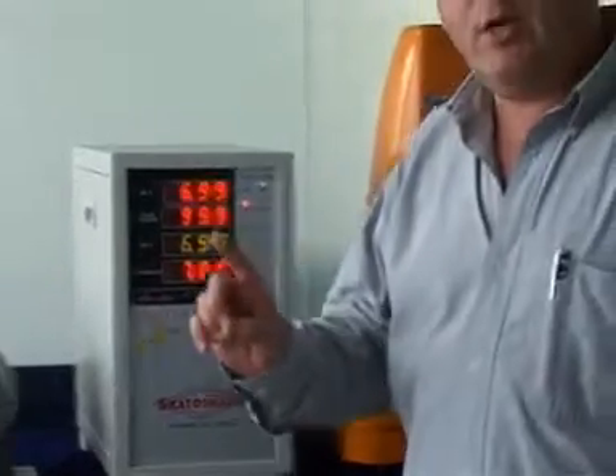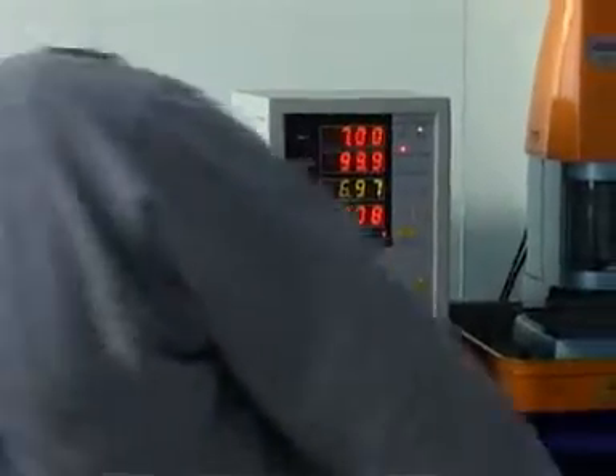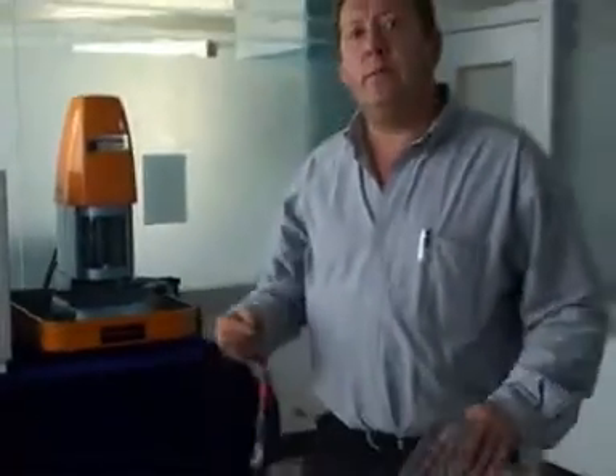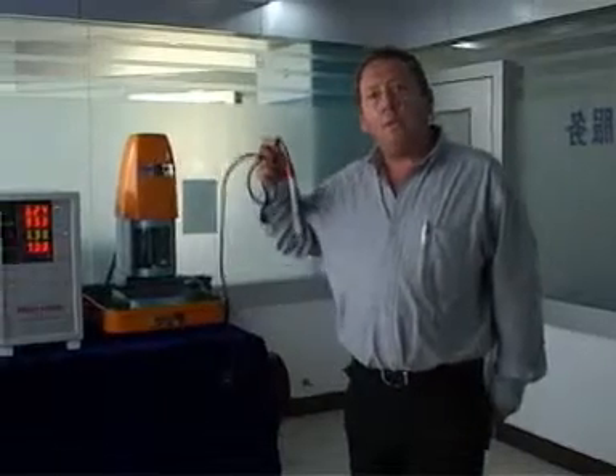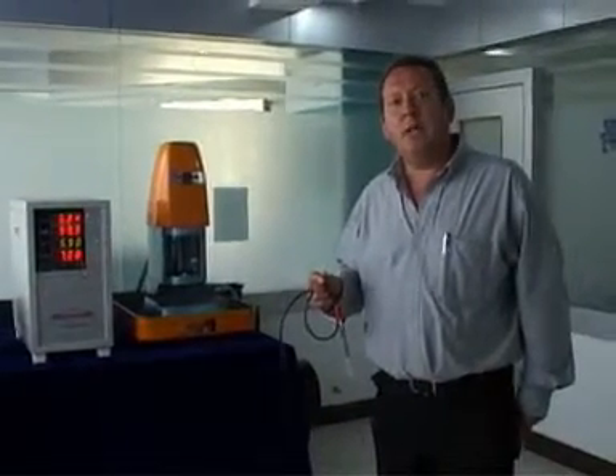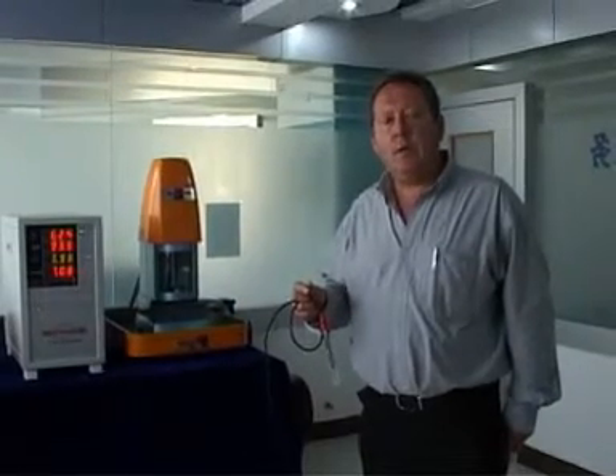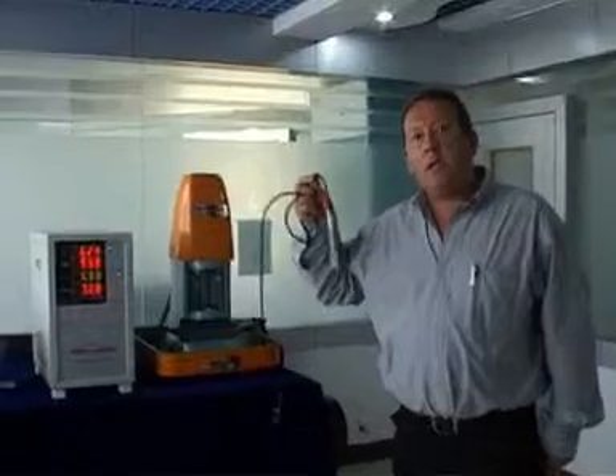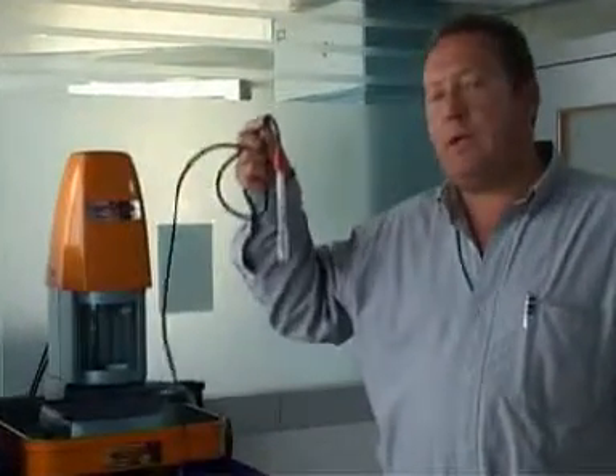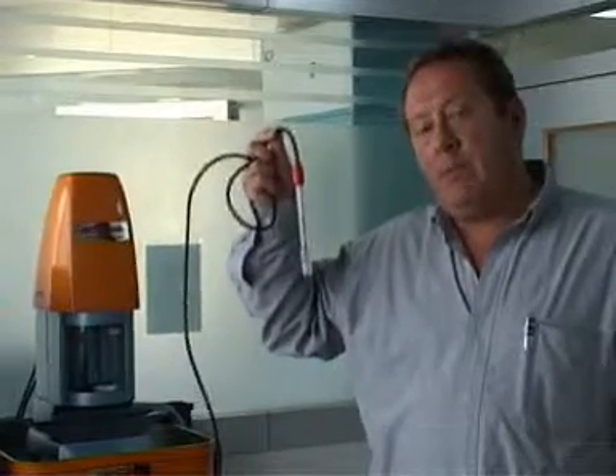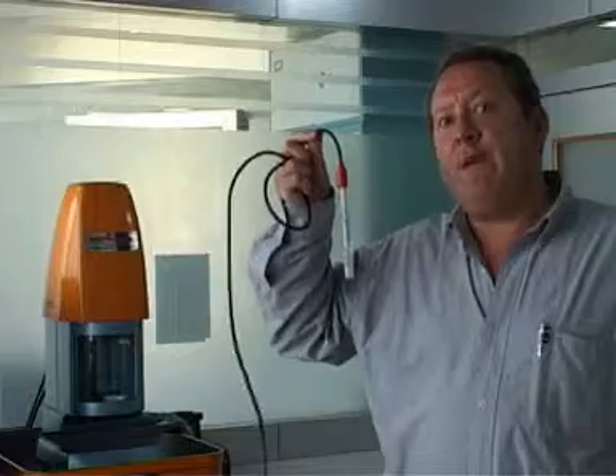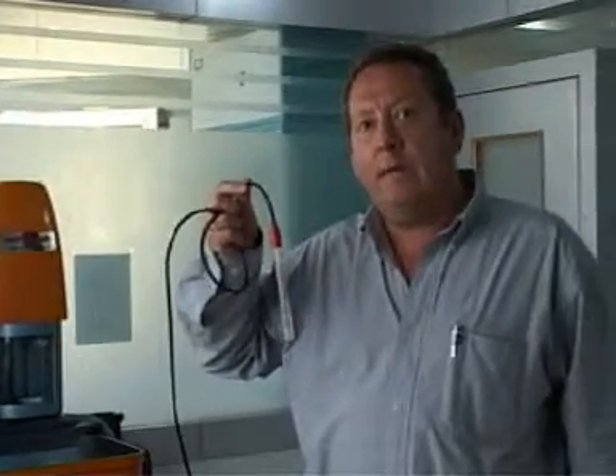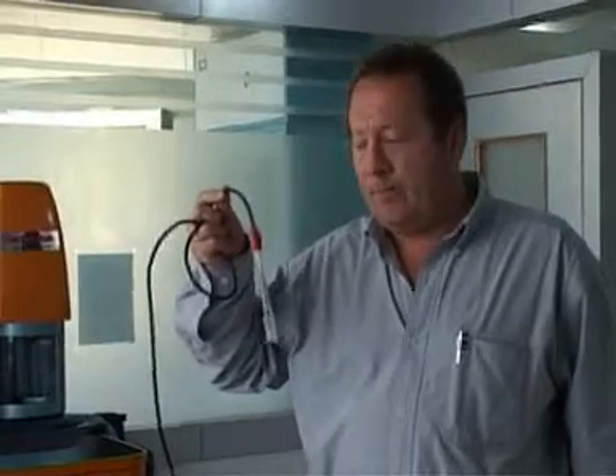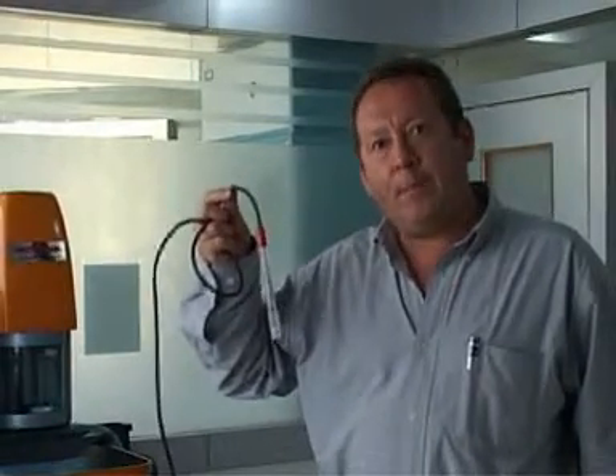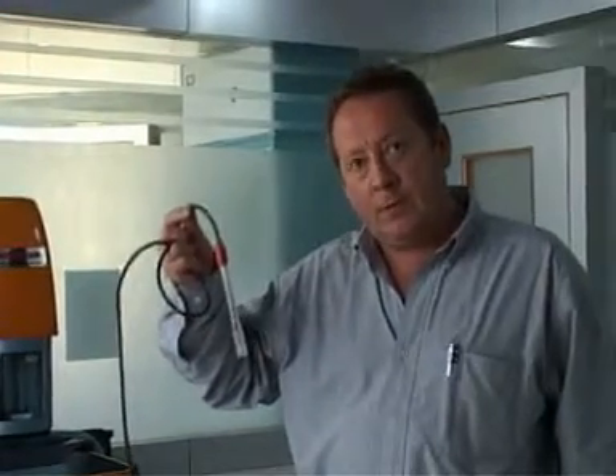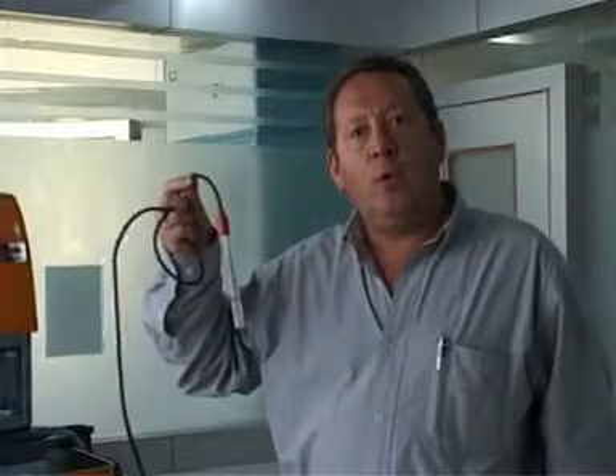There are many methods to measure the pH. There is a manual method to measure the pH, where somebody physically measures the pH and then adjusts the valve, which is very inaccurate. New semi-automatic systems use electrical pH measuring devices, but these devices need to be removed every shift to be cleaned. If scale has built up on the probe during the shift, the reading will not be correct.